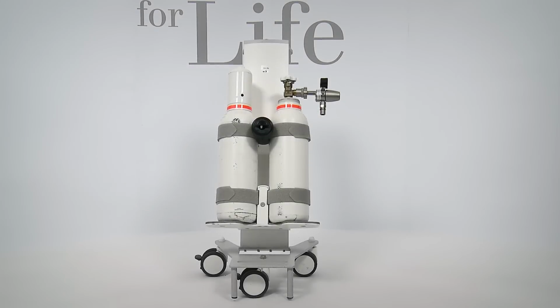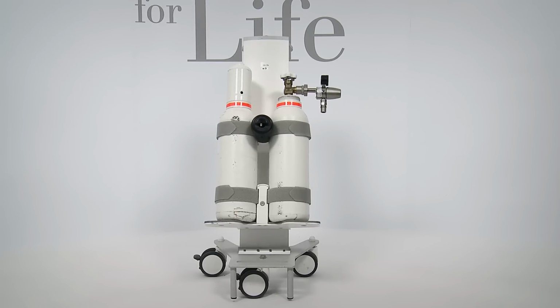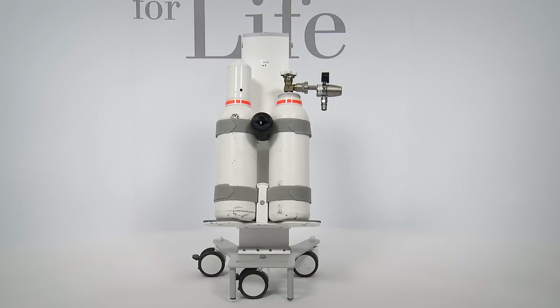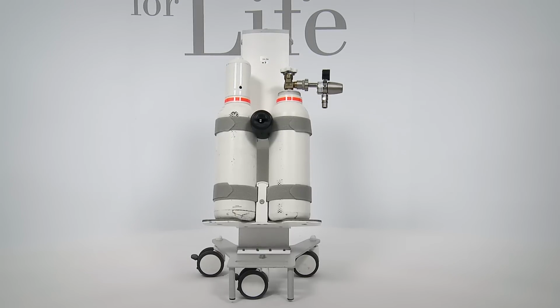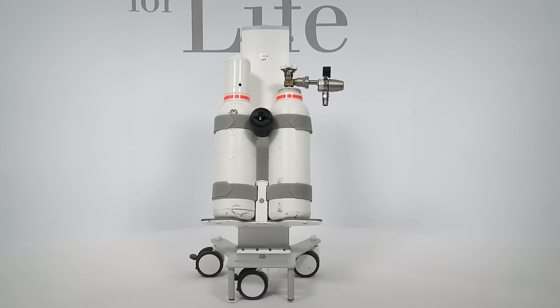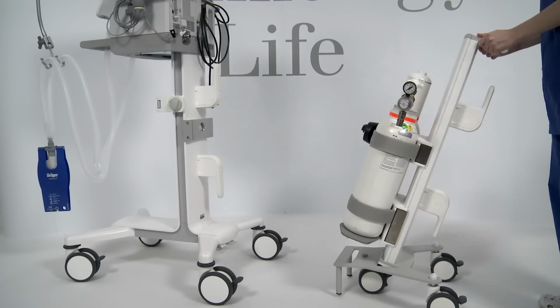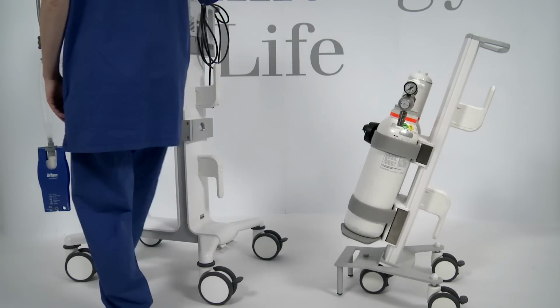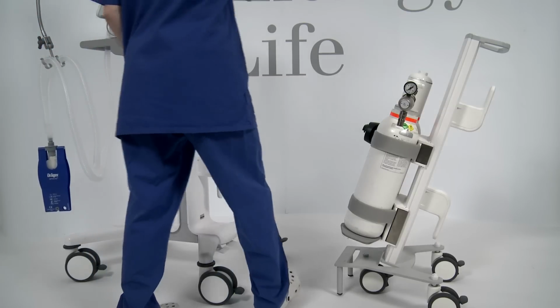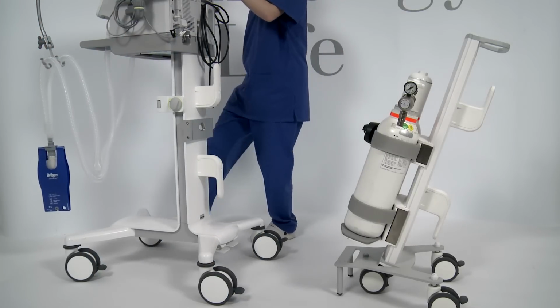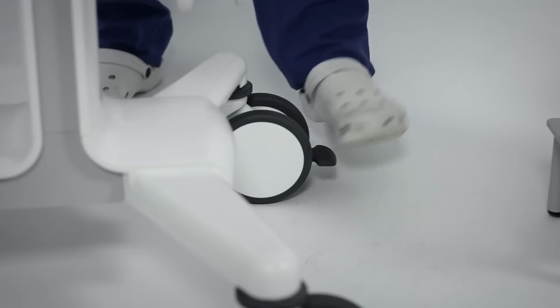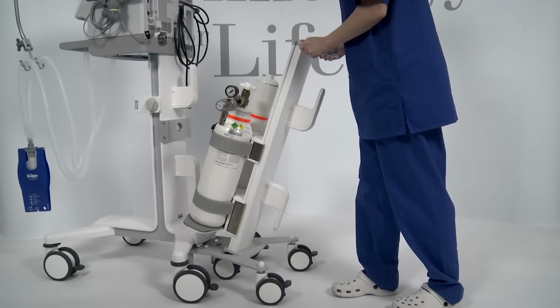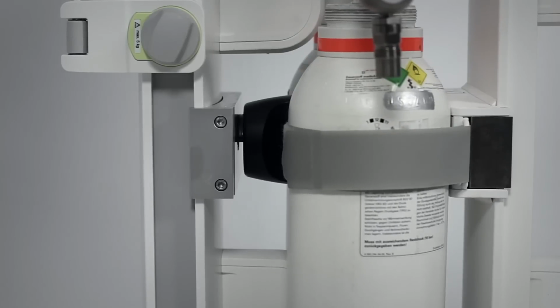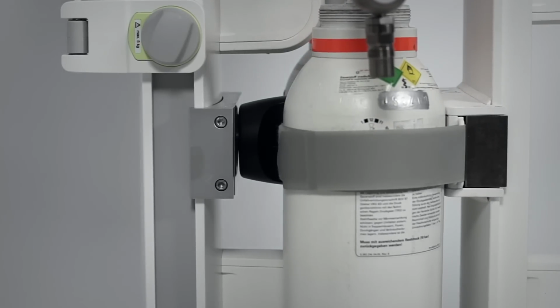The transport supply unit has been designed for a fast coupling to the trolley of the ventilator. The transport supply unit supplies the Savina 300 with gas from 1 or 2 compressed gas cylinders. To couple the transport supply unit with the ventilator, lock all brakes on the trolley of the ventilator. Move the transport supply unit under the trolley. The guide pin must be pushed into the fixing plate. Tip up the transport supply unit until the coupling element of the transport supply unit audibly clicks into the coupling element of the trolley.